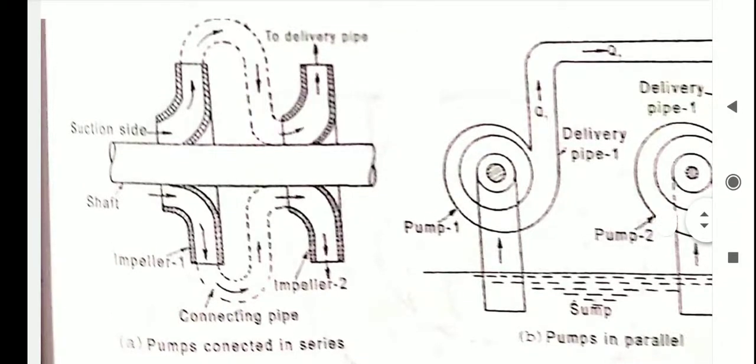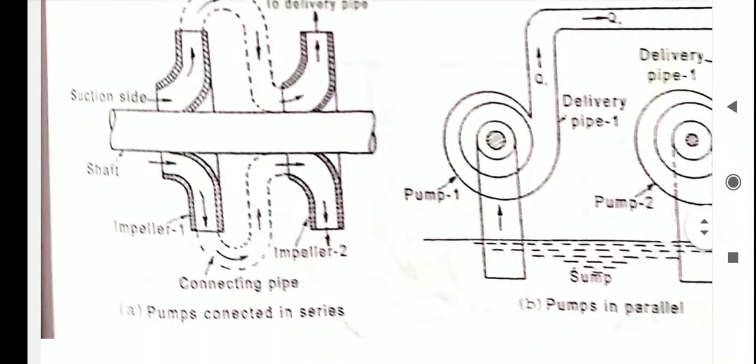The flow is the same in both impellers. The head produced by the combined impeller will be higher. If n is the number of identical impellers and each produces a head of hm, then the total head developed hd is given by n into hm.